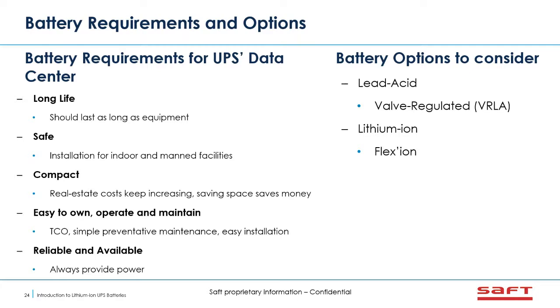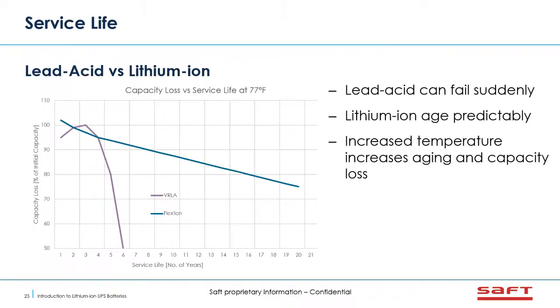And we know that these batteries always need to provide power to their load. And what we're going to compare here is a lead acid battery and lithium ion, and more particularly, the VRLA technology versus a Flexion system. So if you look at the service life, lead acid batteries can obviously fail suddenly. IEEE recommends changing them out once they reach 80% capacity. So here is a graph showing a typical VRLA life versus the Flexion life. You can see it's just a very predictable gradual fade of capacity as it ages. Temperature does affect any technology. The higher the temperature, the shorter the life. So that would be applicable to VRLA, but also lithium-ion batteries as well.